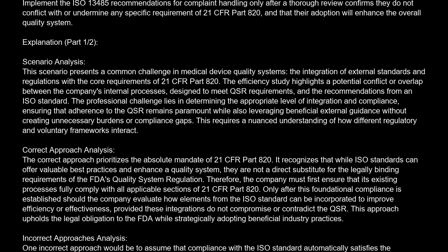Correct approach analysis. The correct approach prioritizes the absolute mandate of 21 CFR Part 820. It recognizes that while ISO standards can offer valuable best practices and enhance a quality system, they are not a direct substitute for the legally binding requirements of the FDA's quality system regulation.